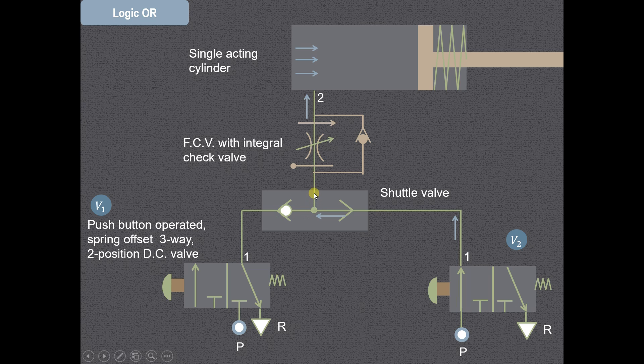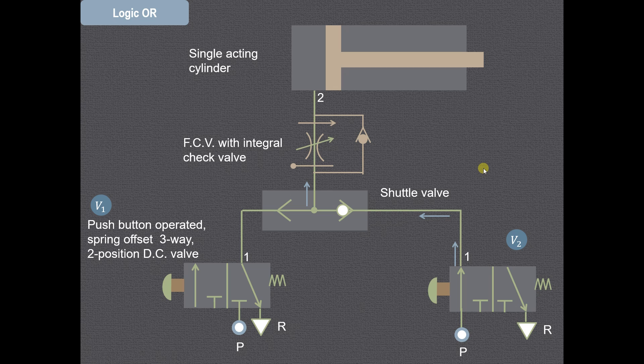The air cannot go through the check valve because this is the no free flow condition, and therefore the air has to go through the restricted opening of the flow control valve. It will then be admitted on the cylinder side of the single acting cylinder, and we will get the operation of this single acting cylinder.